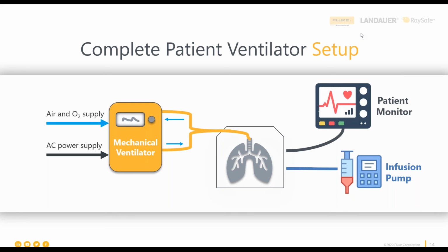realistically, if you had more than one patient you were going to connect to a ventilator, they had better have the same treatment plan as each other. So 1, 2, 3, however many there are. And the ventilator's intended use never covered that. So now you're out in territory about effective delivery that you've never been before, the doctors and nurses have never been before. And so it required additional clinical monitoring, which increased the need for other things than just ventilators in order to make the treatment work.